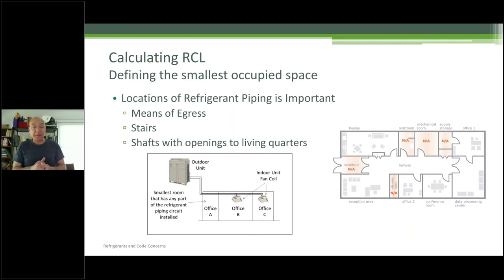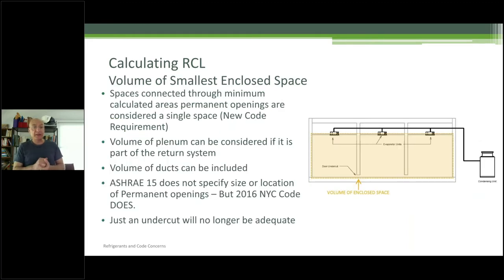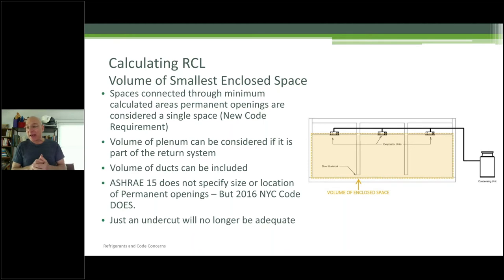RCL calculations need to take the full system charge into account — what is likely to be discharged into one space. Calculating RCL: you've got to define your smallest occupied space and the maximum number. Sometimes it's iterative, depending on the system complexity. You've also got to be careful about means of egress — stairs, shafts with openings to living quarters — it's not a good idea to run refrigerant piping in stairs. A question came in: is introducing door undercuts enough to use the whole apartment as a room for charge-safety calculations? That's exactly what I'm getting to.